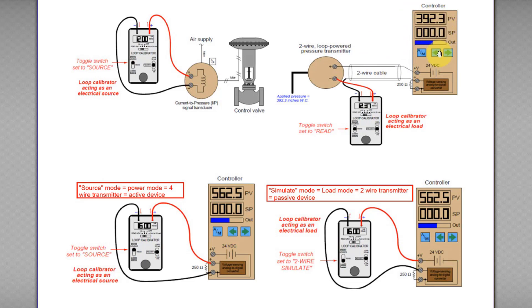The power source must be provided by the transmitter, the controller, or an external power source. In this case, the controller will act as an electrical source to provide the power to power the whole load. You can see there is a wire connected to the positive V, which stands for positive voltage source. This positive V is internally connected to the controller's internal power source. That's why this terminal will act as an electrical source, and the internal power will power the whole load — so this transmitter and the signal calibrator here will act as electrical load.